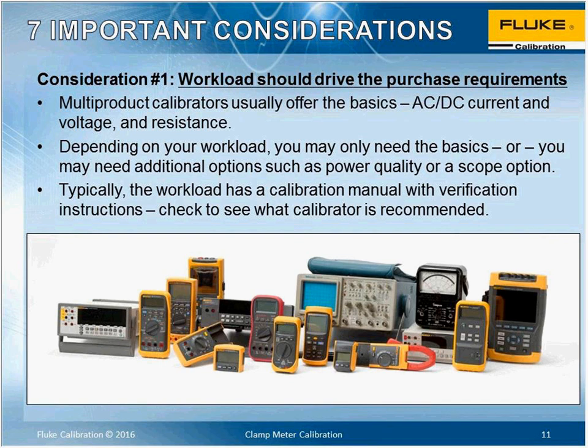Typically the products will have some sort of service manual or calibration manual associated with them, and hopefully inside that manual they've given recommendations on what type of products you can use that would have good enough accuracy to give you at least a 3-to-1 or 4-to-1 test uncertainty ratio. But this is the starting point. What I find is that if you have a good list of requirements, the shopping process is very easy, because now you can talk to the representatives of whatever company you're talking to about those requirements.